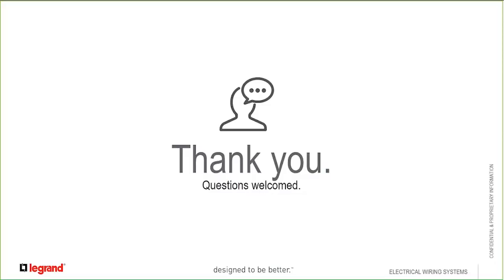Suitability rating? Suitable rating? Not really familiar with that. We might have to take that one offline. Okay, moving on. Do you recommend everything on the circuit, including lighting, be put on a load side of a GFCI, or just the receptacles? Yeah, that would be fine. Doing it that way would be fine. Okay.